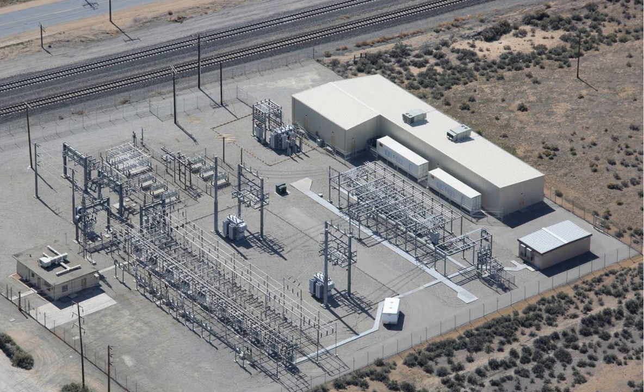The TSP system is constructed of 608,832 lithium-ion battery cells that are enclosed into 10,872 modules of 56 cells each and then stacked into 604 racks. A bidirectional inverter or power conversion system, PCS, provides the DC to AC conversion during battery discharging and AC to DC conversion for battery charging. The batteries are housed in a 6,300 square foot, 590 square meters building. The TSP system can supply 32 megawatt hours of energy at a maximum rate of 8 megawatts. This is sufficient to power between 1,600 and 2,400 homes for 4 hours. The amount of energy stored at TSP is equivalent to that stored in more than 2,000 Chevrolet Volt hybrid electric vehicles.